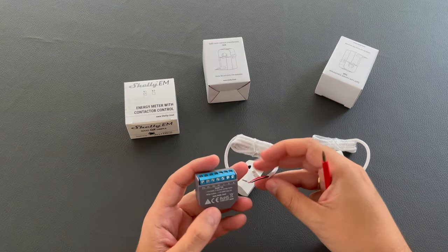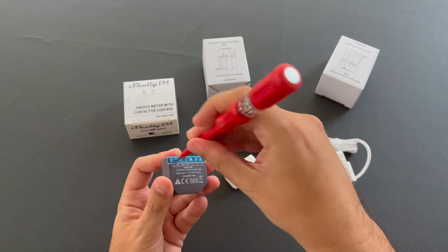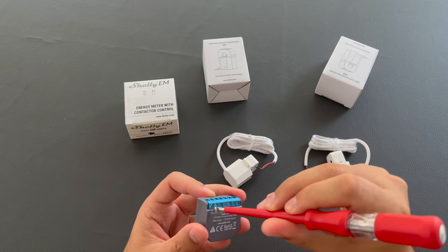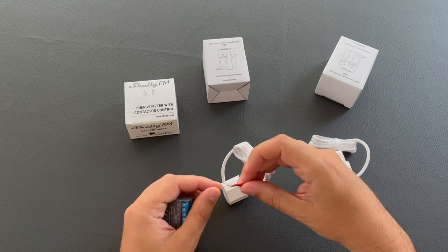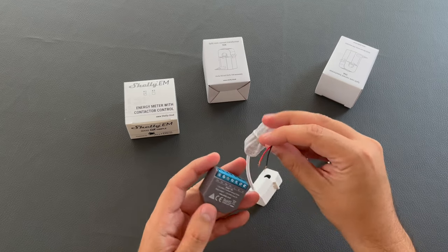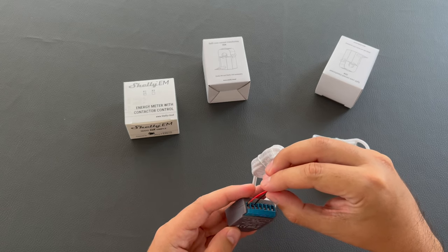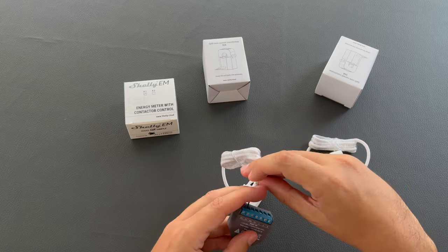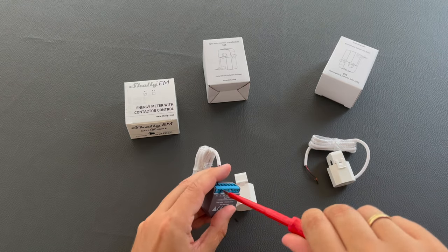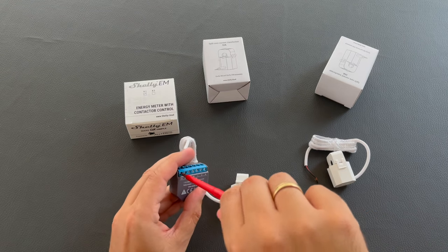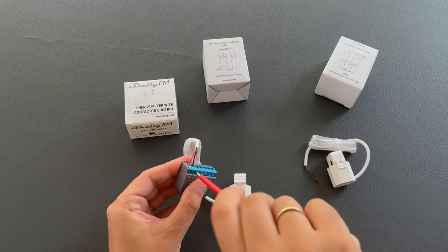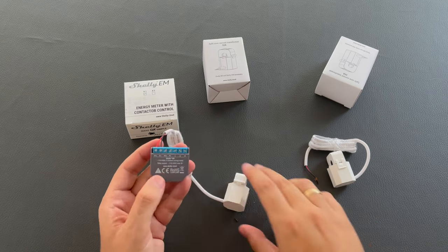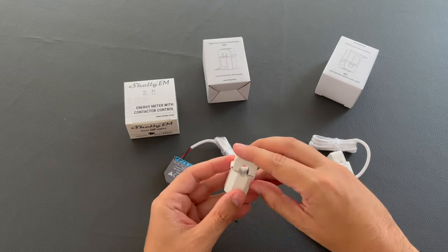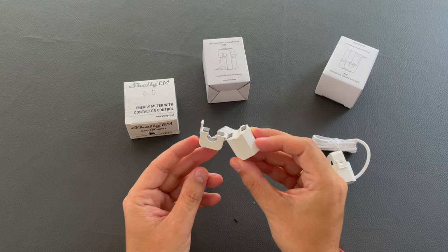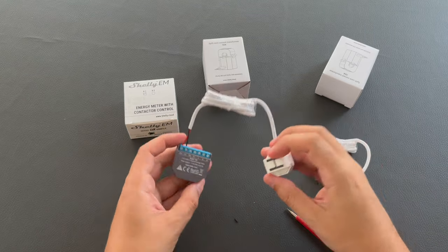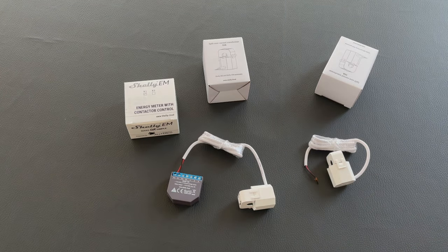Now it's time to connect the current transformer to the Shelly EM. We need a small screwdriver and connect the first current transformer to the connection of P1. Don't forget we have a P1 plus and a P1 minus connector. This is how you connect the current transformer to the actual Shelly EM. Then you open this clamp here and make sure that this will be around the cable you want to measure the power consumption. Same procedure for the second clamp, but this time this needs to be connected to P2.